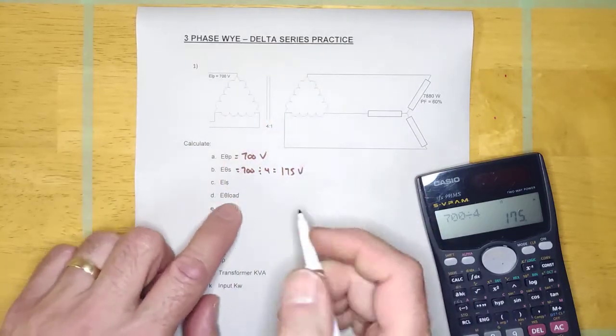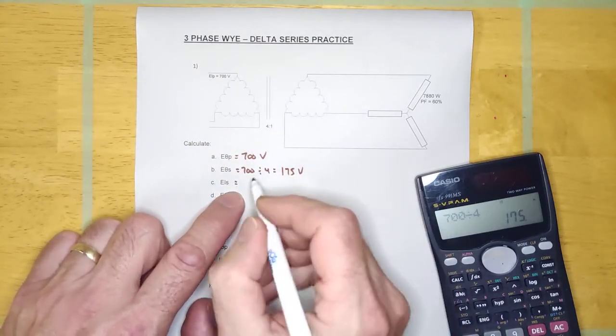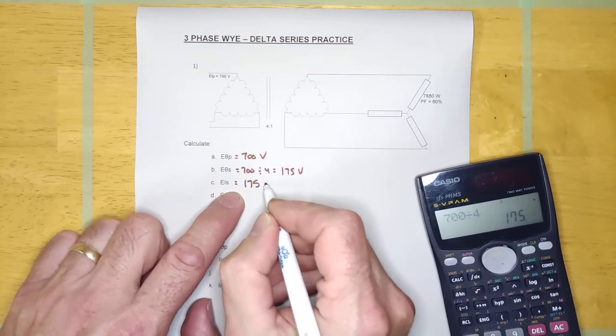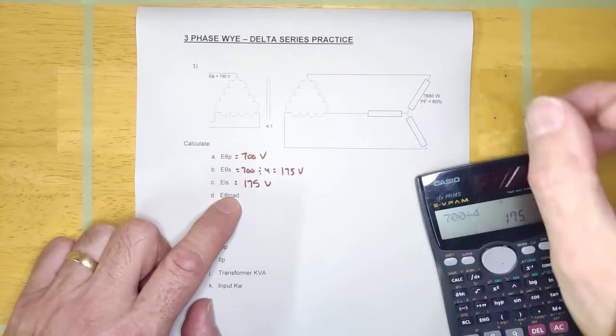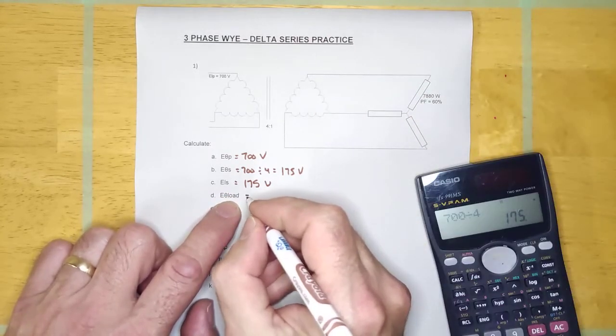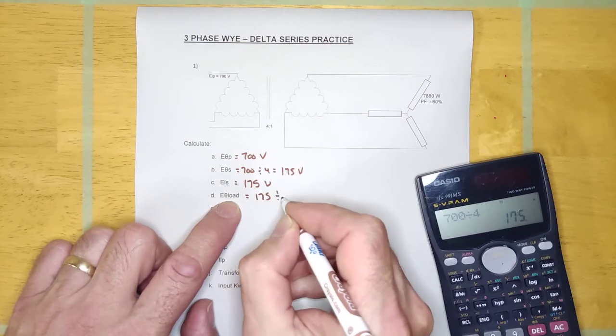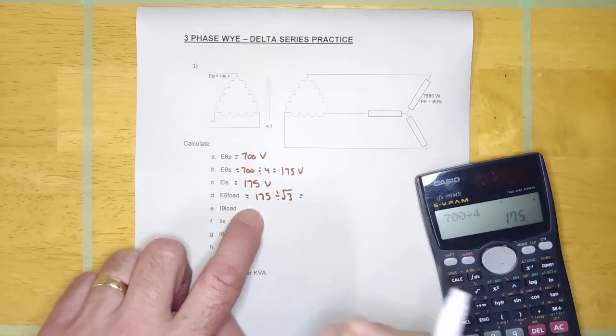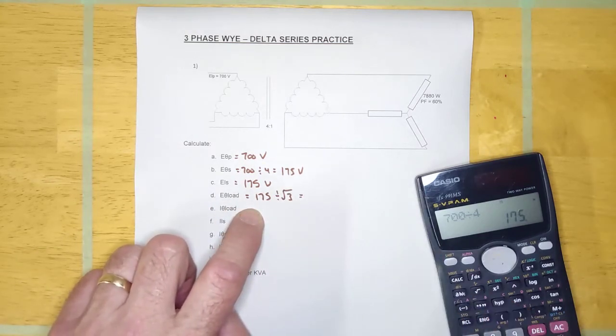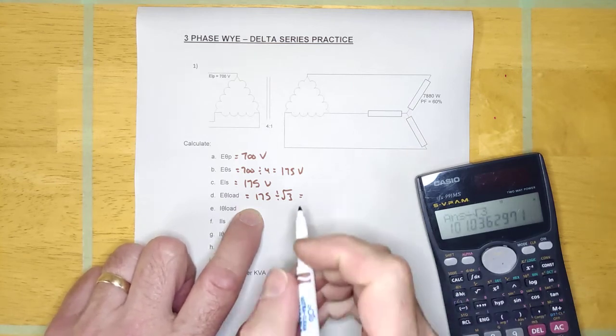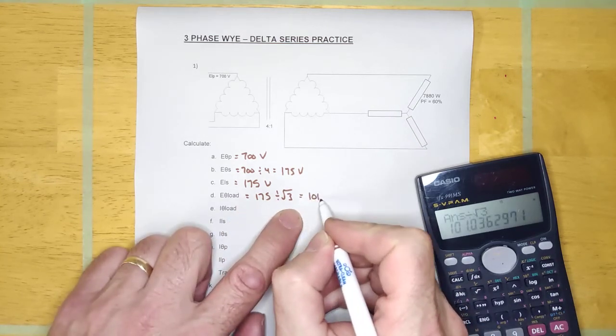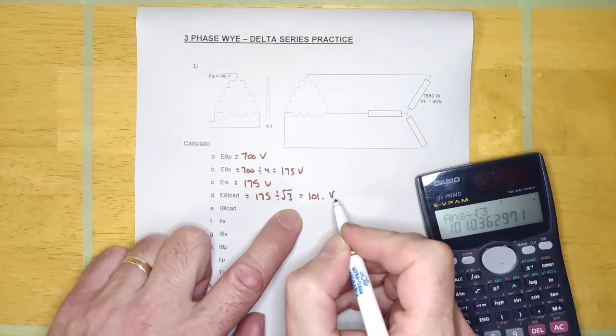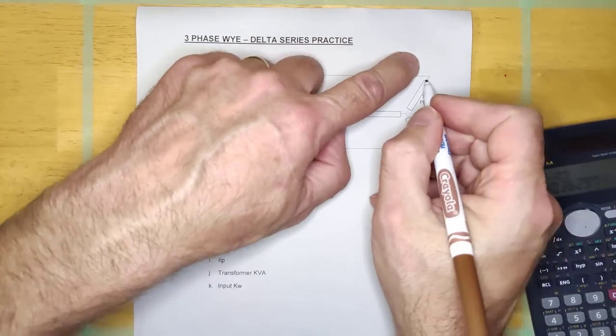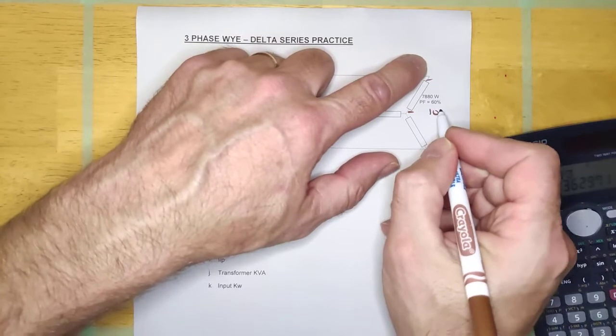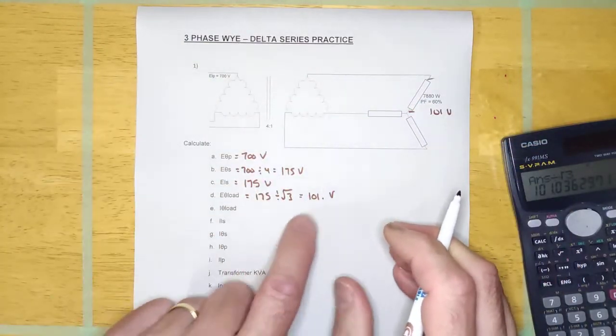Again it's delta, so our line voltage is going to be the same on the secondary side, 175 volts. Then this is Y, so it's going to take that 175 divided by root 3. Divided by root 3, and it looks like we get 101 volts. That would be measured here, right guys? 101 volts, E-phase load.